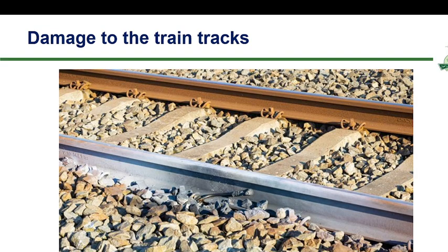All right. This slide is illustrating the physical consequences of a sagging transmission line on nearby infrastructure, especially railway tracks. When a transmission line sags and the clearance is exceeded, it can come into unintended contact with surrounding objects, such as rail tracks. In this case, the figure shows clear damage to the rail, likely caused by electrical arcing or fault current passing through the metal structures.